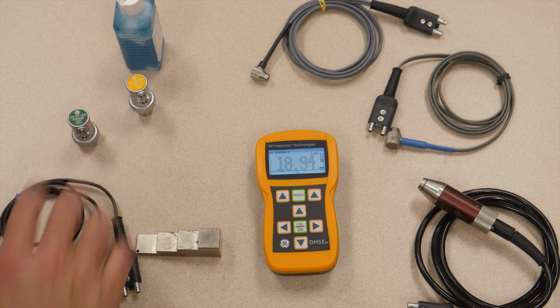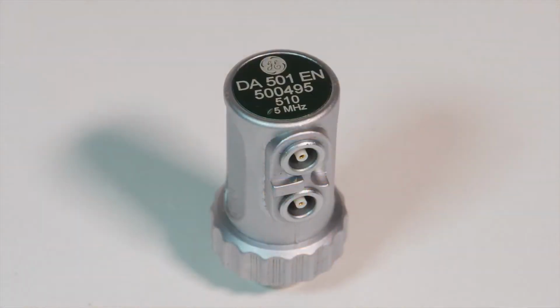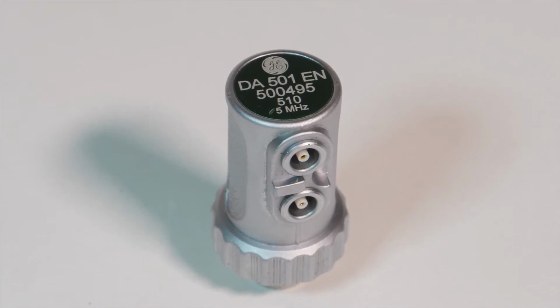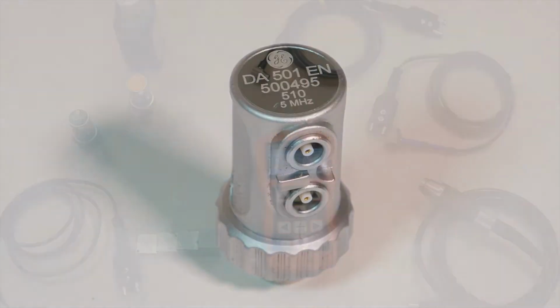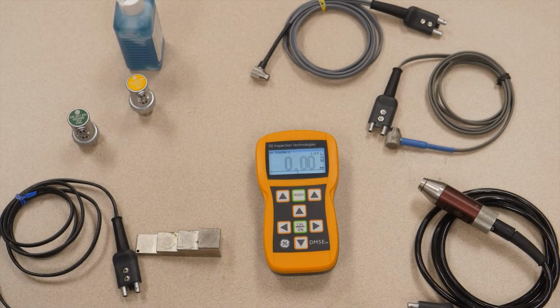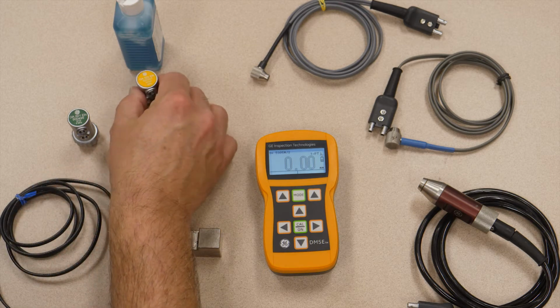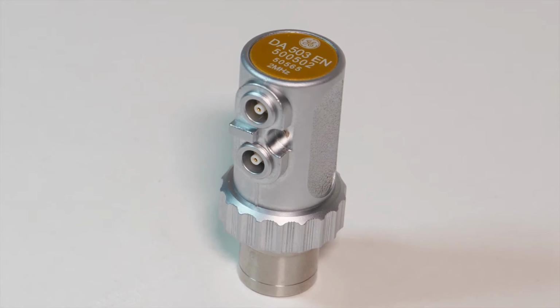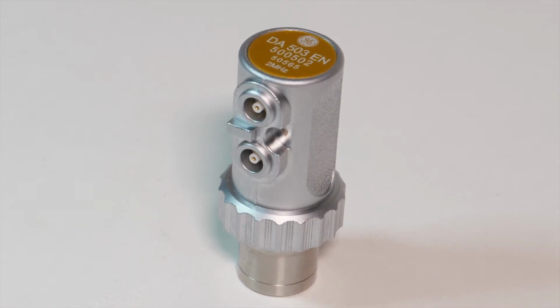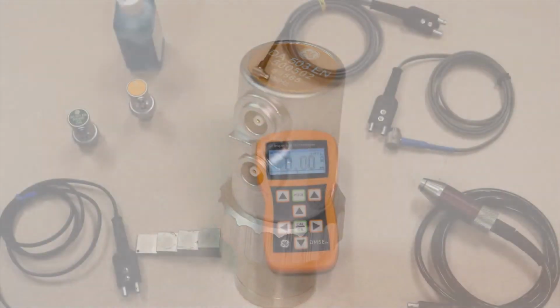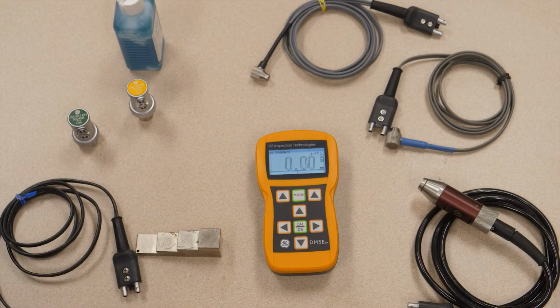The DA501 is probably the most commonly used probe with the DM5E. It is a 5 megahertz general purpose probe, has a measurement range of about 1 millimeter to 200 millimeters, 40 thousandths of an inch to 8 inches. The DA503 is a lower frequency, larger diameter probe. It is ideally suited to coarse-grained materials, highly attenuative materials, thicker materials. With the DA503, you have a measurement range of 5 millimeters to 300 millimeters, or about 200 thousandths to 12 inches. All right, so thicker materials, DA503.